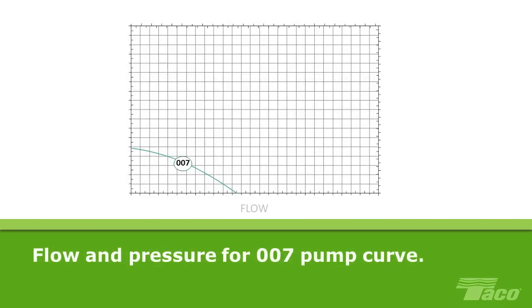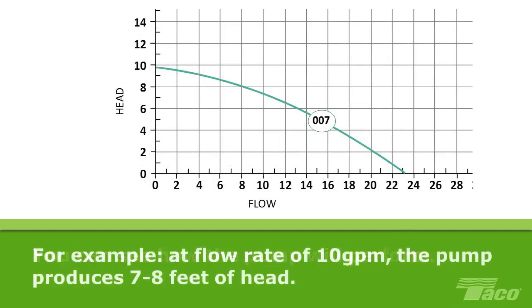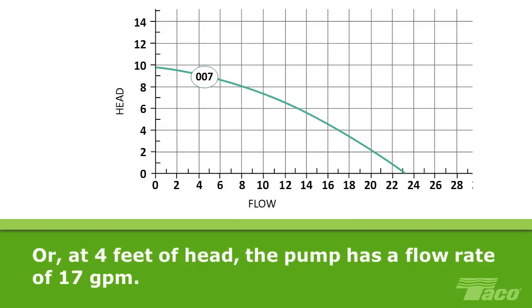Let's see how these two factors look on a pump curve graph. The curve enables you to see how this pump will perform at any given point within its performance range. For example, at a flow rate of 10 gallons per minute, the pump will produce between 7 and 8 feet of head. Or, looking at it the other way around, at 4 feet of head, this pump will generate a flow rate of just about 17 gallons per minute.